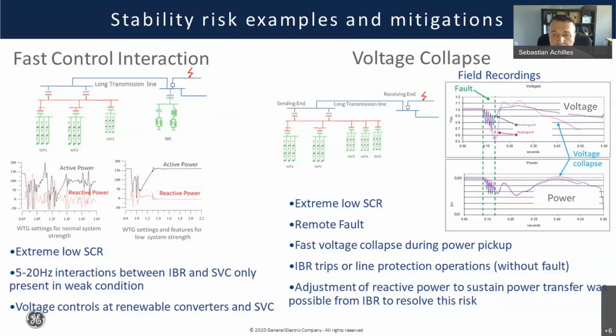After that, there is a synchronization event. And then you can see that around 0.25 seconds in those plots, the voltages are relatively high because you're pushing less active power through the system. So the charging of the line tends to bring the voltages high, and the power is relatively low. At that point, the wind turbines decide to start increasing the active power. And from that on, you see a voltage collapse. As the power increases, the voltage decreases, and it ends up collapsing the system. This collapse is very quick. If you look at it, it's 200 milliseconds, and you collapse this huge system.